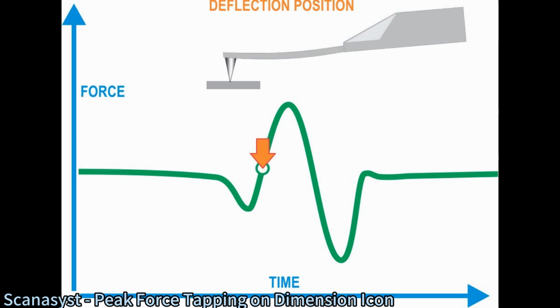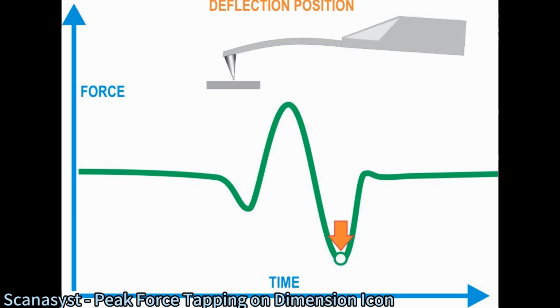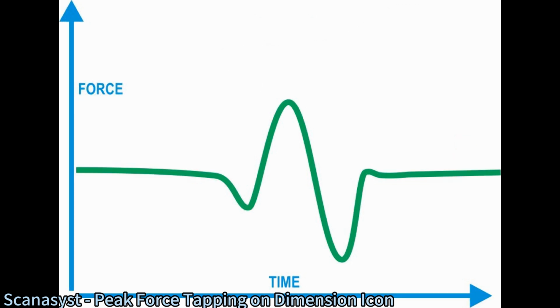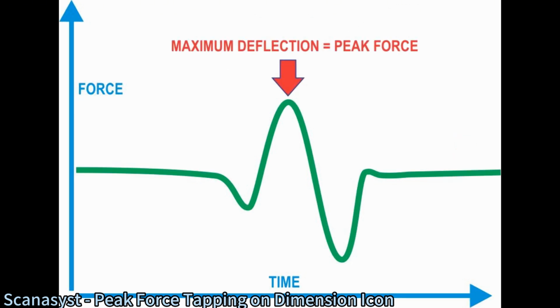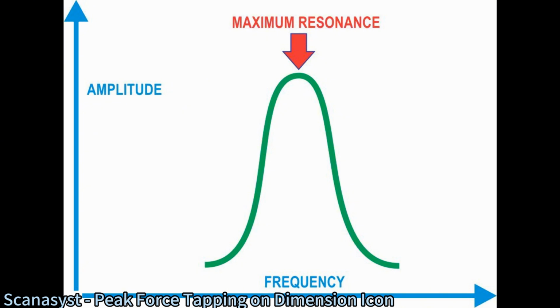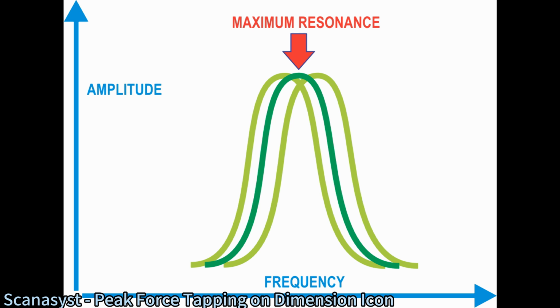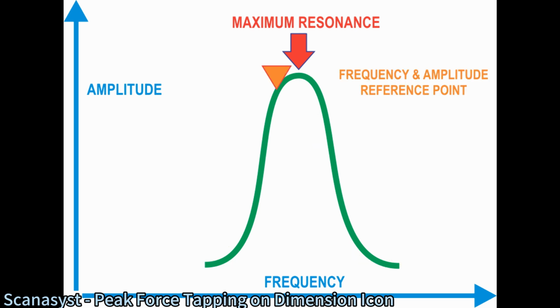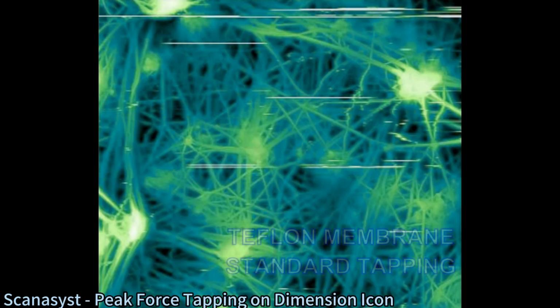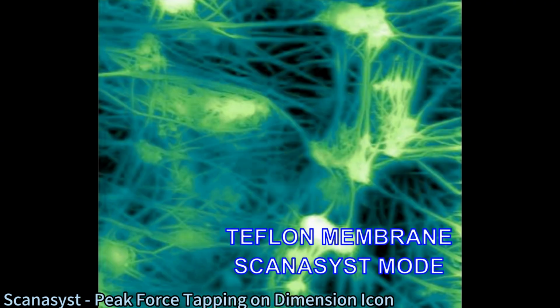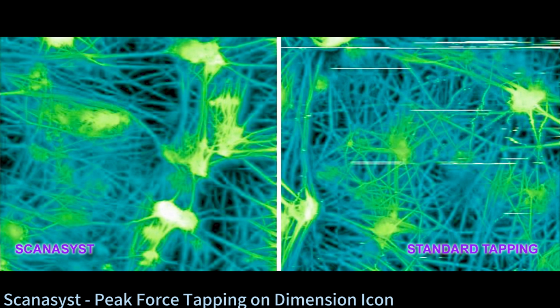The system monitors the force curve to identify the point of maximum tip deflection, or peak force value, which is then utilized to control the feedback loop that drives the scanner piezo and thus the position of the probe in relation to the sample. Standard tapping mode monitors the shift in frequency or amplitude of the resonating probe and generates an image based on the response of the probe to the force gradient above the sample surface. But the data from the peak force cycle is used to maintain the optimum interaction between the tip and sample as the tip rasters across the sample surface. Peak force tapping is the feedback technique that makes ScanAsyst mode possible. The result is an improvement in image quality when compared with standard tapping mode.